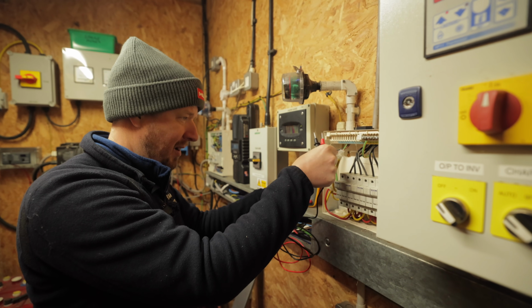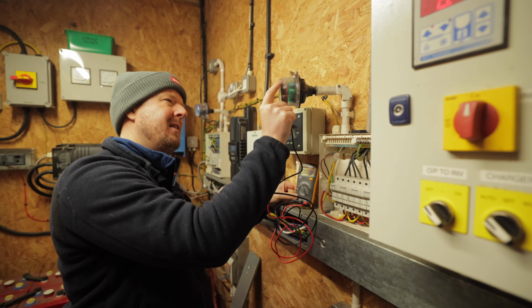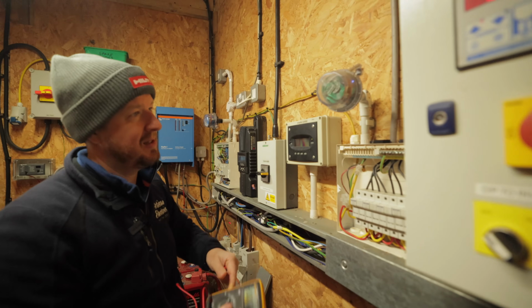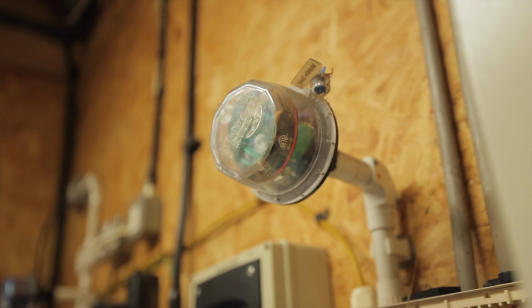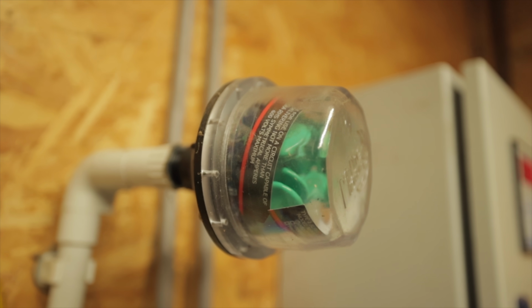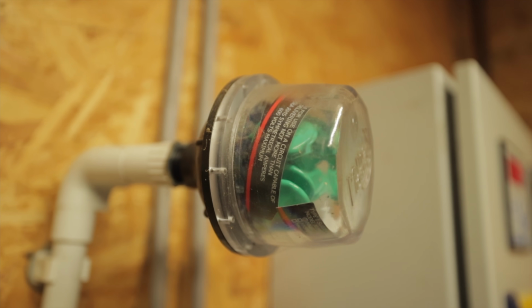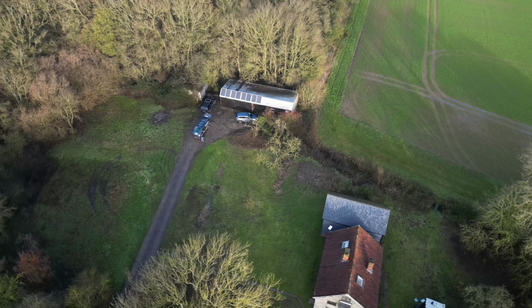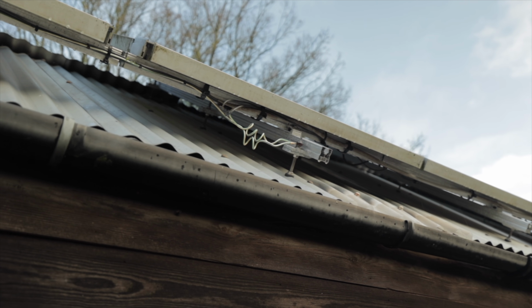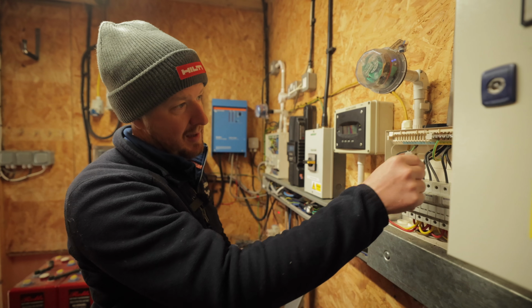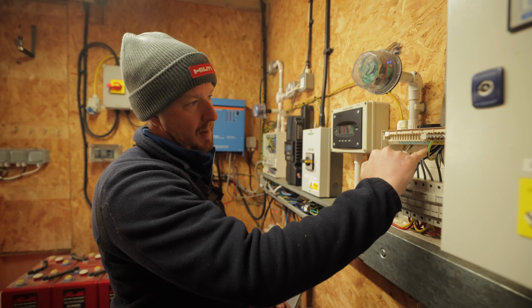And then they've put this kind of capacitor thing, type 1. Oh, it's a surge protection device. Wow, that is interesting, I've never seen a DC surge protection device like that before. That's quite good. I guess because it's in the sticks and it's on a metal roof, they've actually earthed the array, so you can see they've run in these earth wires.